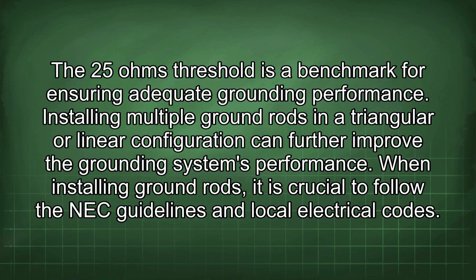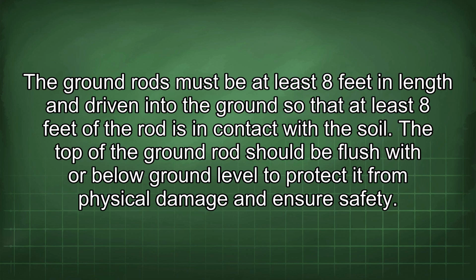When installing ground rods, it is crucial to follow the NEC guidelines and local electrical codes. The ground rods must be at least 8 feet in length and driven into the ground so that at least 8 feet of the rod is in contact with the soil.